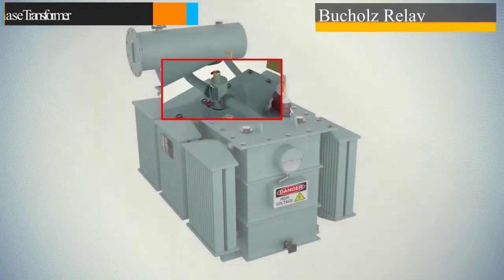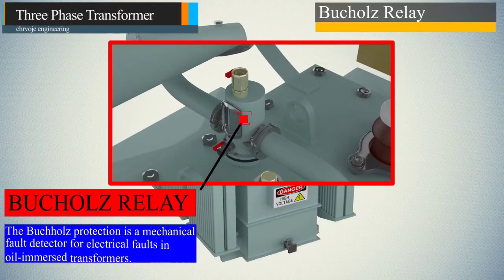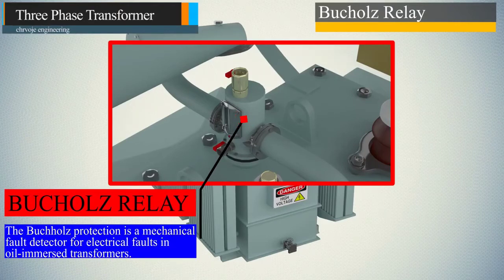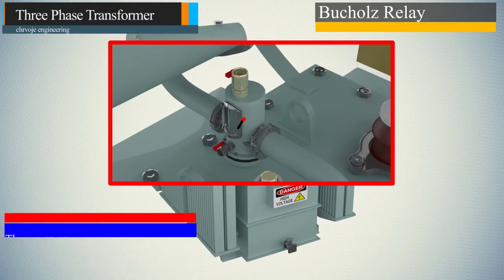The Buchholz protection is a mechanical fault detector for electrical faults in oil-immersed transformers. The Buchholz gas relay is placed in the piping between the transformer main tank and the oil conservator. Buchholz relay reacts when any fault occurs inside the transformer. The transformer oil gets decomposed and gas bubbles are produced. These gas bubbles move towards the conservator through the pipeline and Buchholz relay reacts on this fault.